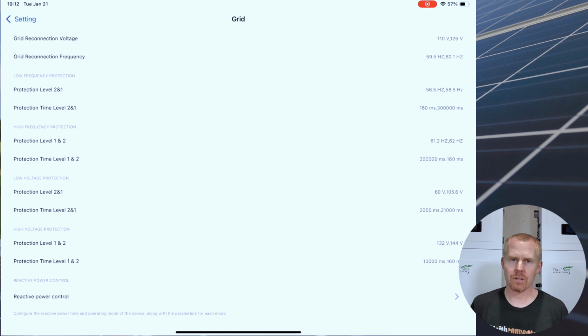A lot of the rest of these settings are going to be the allowable ranges for your grid connection. These probably shouldn't be changed unless you consult with your distributor first to get their recommendations. They're here to allow you to correct some grid issues, but I wouldn't go messing with them without hearing from your distributor or from MidNite directly.